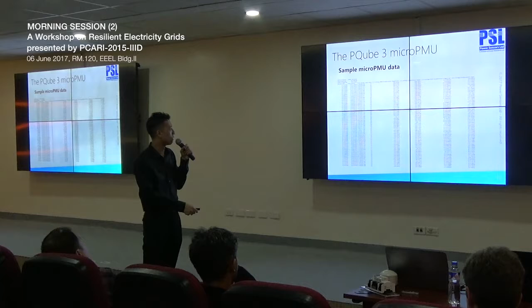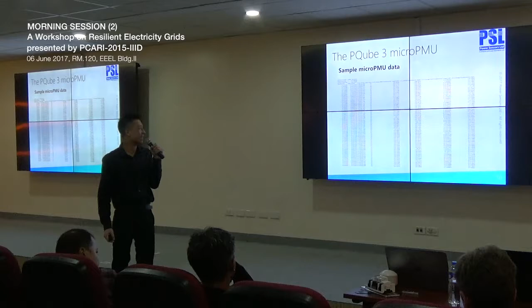Before I get to that last part, here's a sample of what the PMU data actually looks like. I grabbed some data out of a PMU I've worked with recently—well, recently meaning 2016. Every row represents 1/120th of a second. You'll see your date and time. The log state indicates the health of your PMU. If it's a non-zero value, or 32 in our case because we implemented some new parameters, but basically 0 or 32 indicates everything's operating okay. If you have a 2, 4, or 8, it indicates you've lost GPS or there's some other issue making your measurements unreliable.